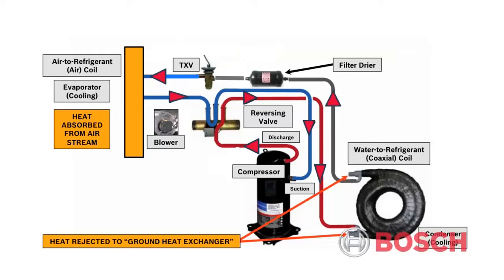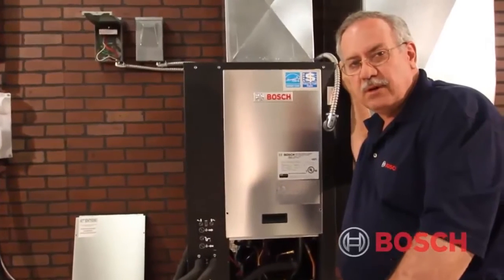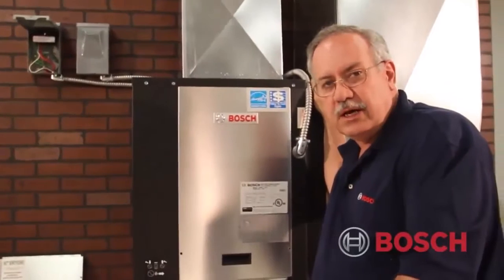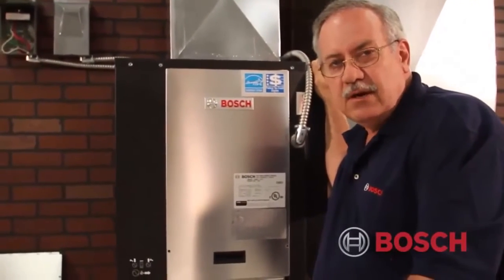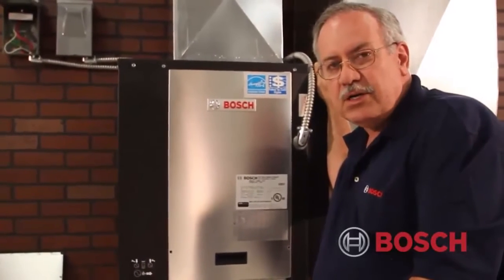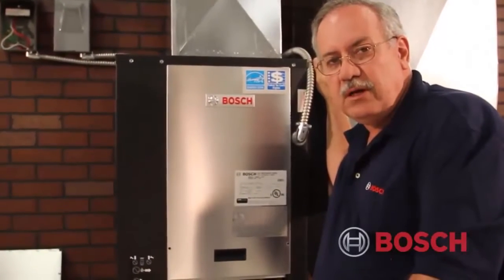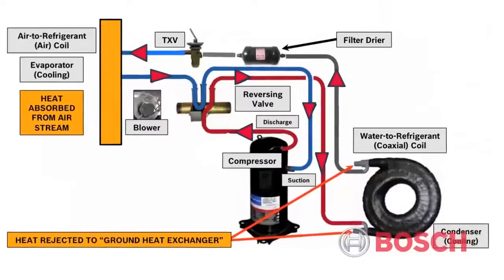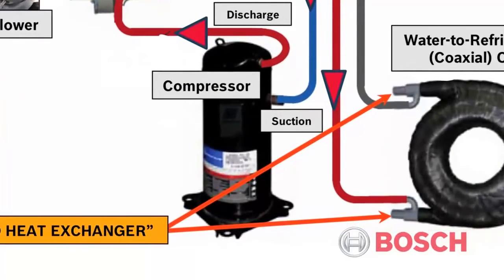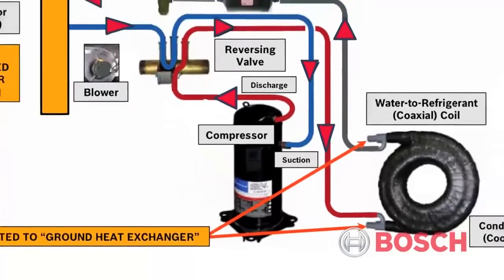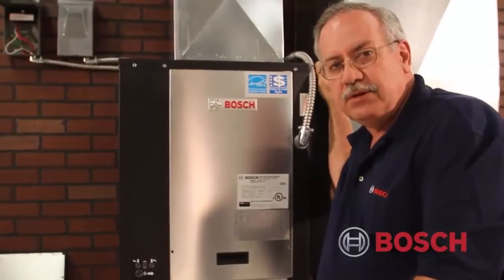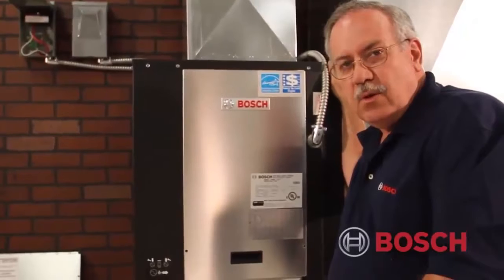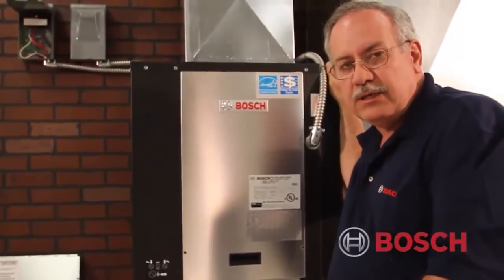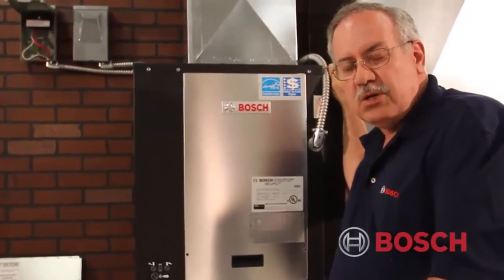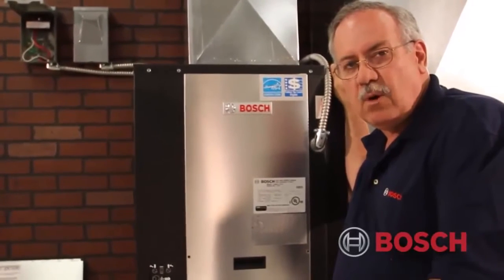Now if I do have to check it in cooling, then I could energize it or change it from one mode to the other in the winter and check it in the heating cycle. In the heating cycle, the refrigerant will approach the operating metering device first instead of the dryer. So additionally, we want to check it in full load. Now this particular unit has an Ultratech Copeland compressor in it, which is capable of 67% first stage in heating or cooling and 100% in full stage, or Y1 and Y2. We'll always want to check the unit in the waterside diagnostics in full load. That means either jumping it out or calling for it and keeping it in Y2 mode.